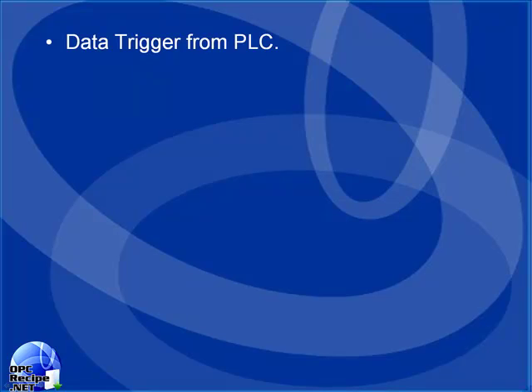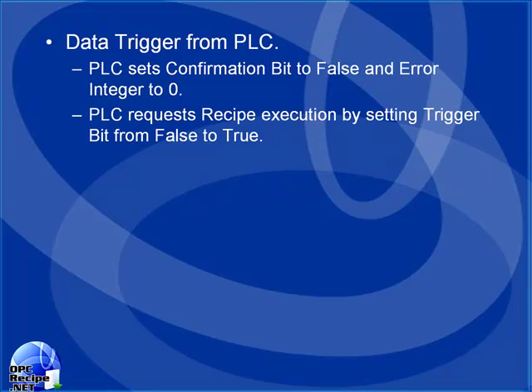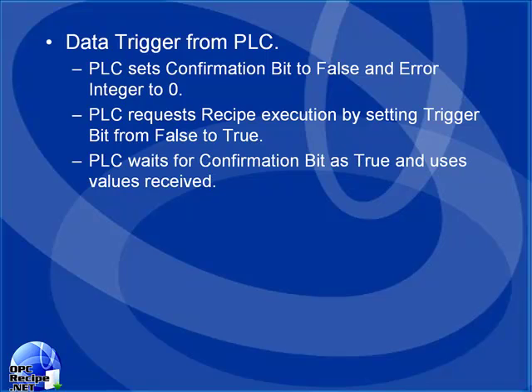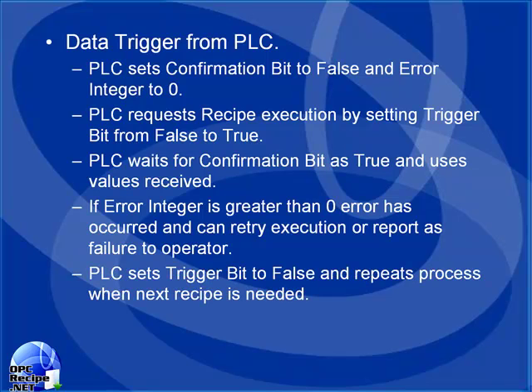Let's see how we would use the confirmation and error feedback in a typical PLC request for a recipe execution. The PLC would first set its confirmation bit and error integer to zero. Then the PLC would request the recipe execution by setting the trigger bit from false to true. The PLC would then wait for the confirmation bit to be true if the recipe execution was successful. If the recipe execution fails, the error integer will be set to a non-zero value, and then the PLC can either retry the recipe execution again or report a failure to the operator. Once the recipe execution has completed, the PLC will then set the trigger bit back to false, and then repeat the process when the next recipe is needed.